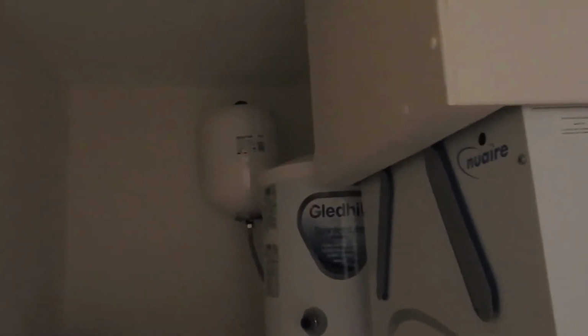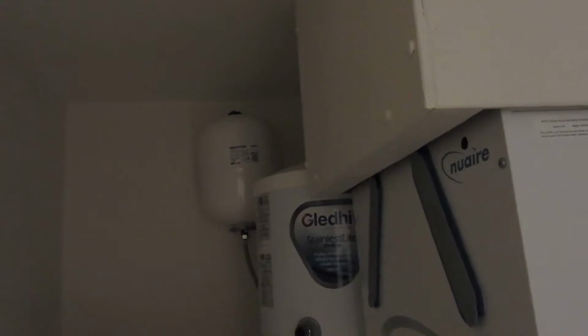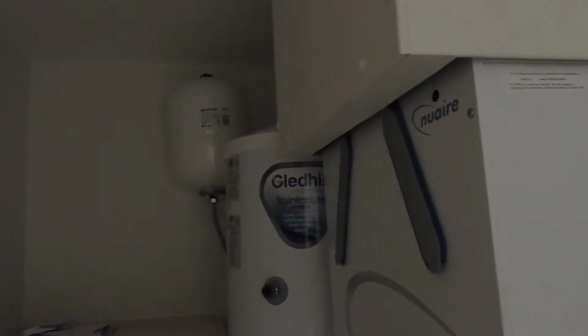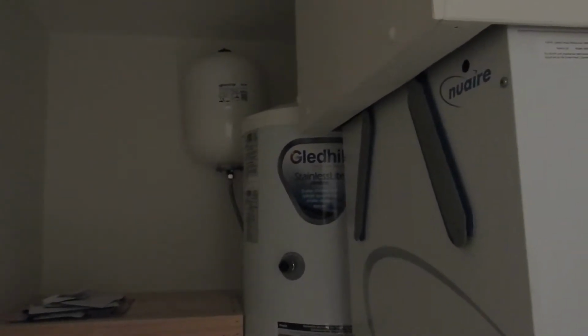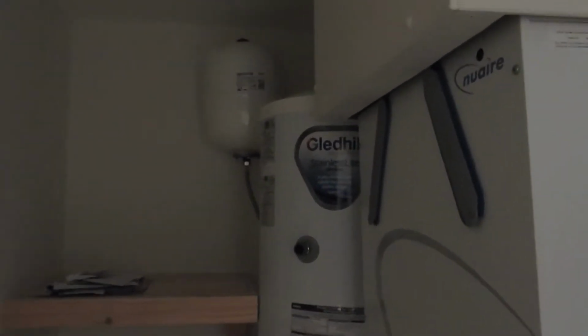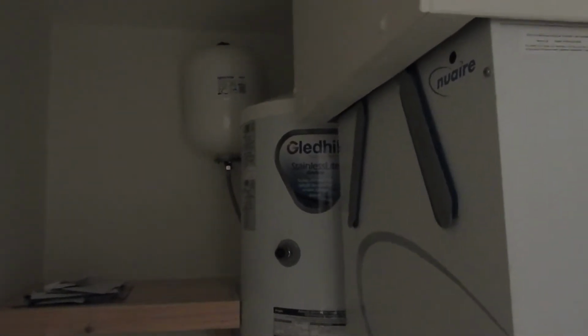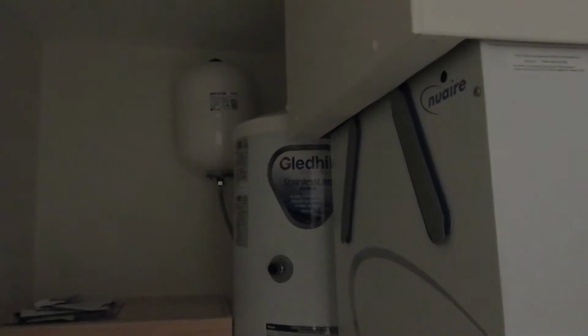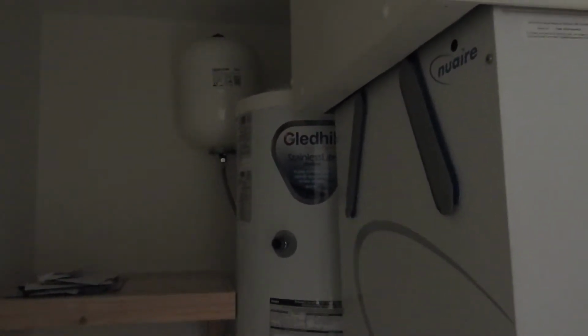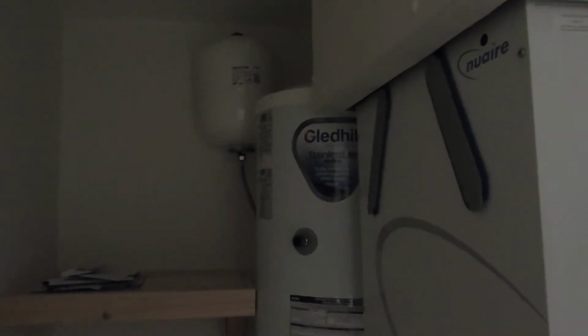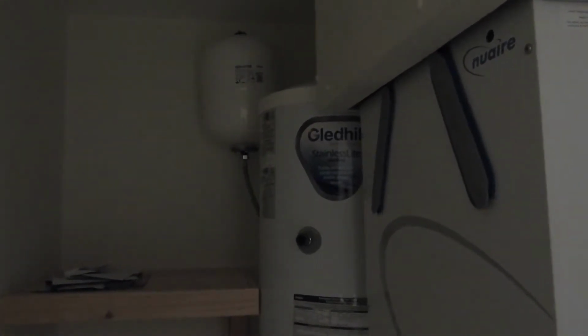Up there will be an isolation valve, and then the water comes into the building, into the apartment, and in here. Now everything is turned off as far as heating is concerned and as far as the boiler is concerned. But what it does mean is this whole apartment is what I would classify as one big dead leg. And once a week I need to come in here and run the water so that fresh water comes into this apartment, and therefore any potential for Legionella to get active is eliminated.